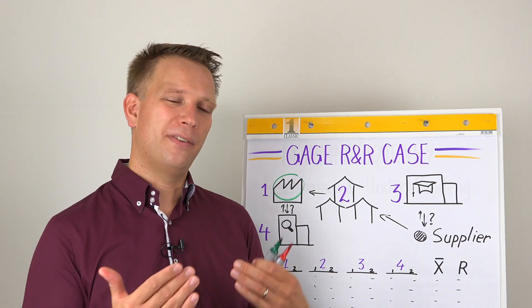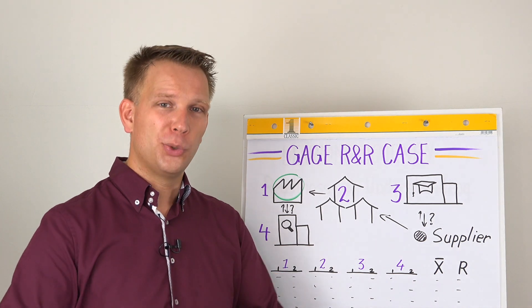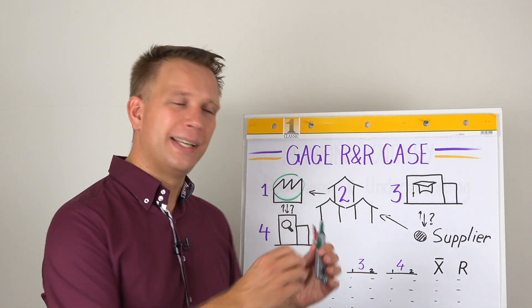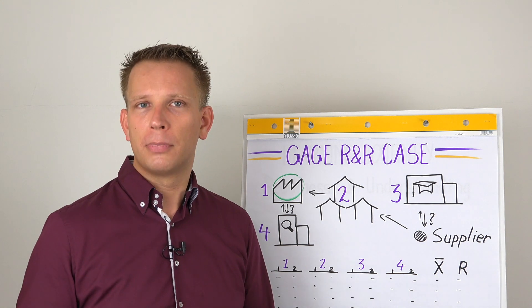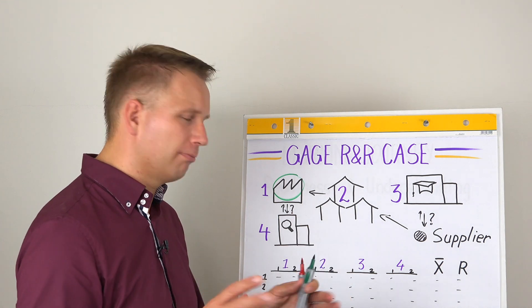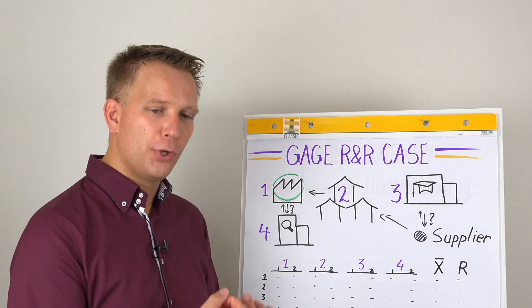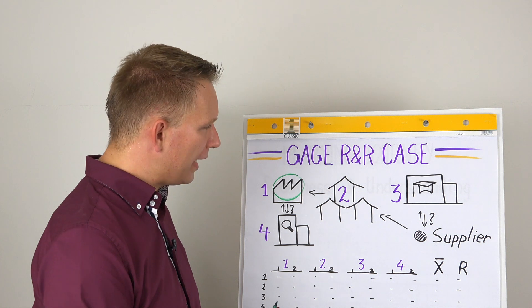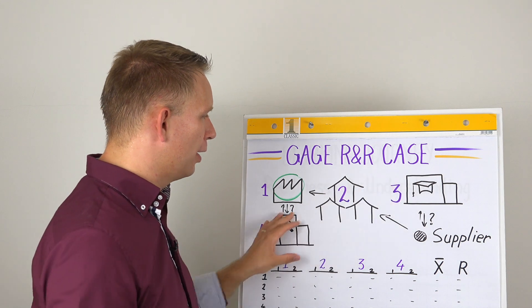that we knew have a bit different contents in the milk, because always with a Gauge R&R you would like to have the whole spread of your process. That makes that you can compare the variation in the analysis with the variation in the actual product that you are getting in. So we took a number of supplier farms that we knew had a difference between what they would give us, and from each of those tankers of milk coming in we took samples and we made sure that we had enough samples to supply all of these laboratories.